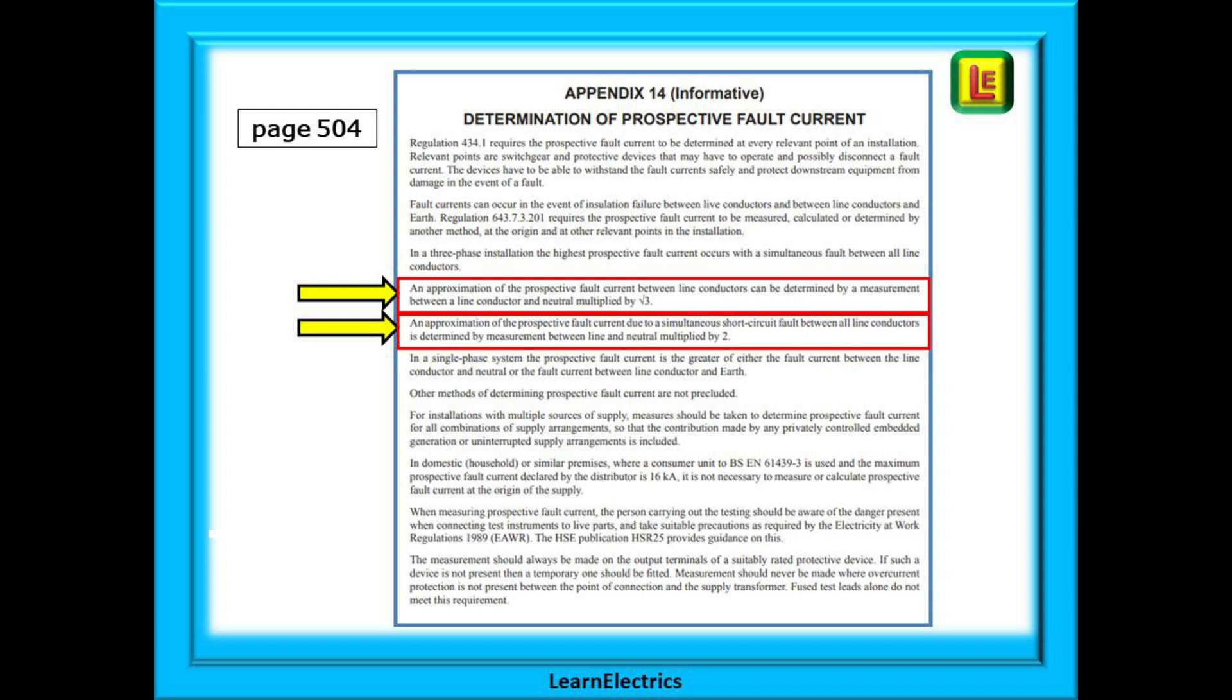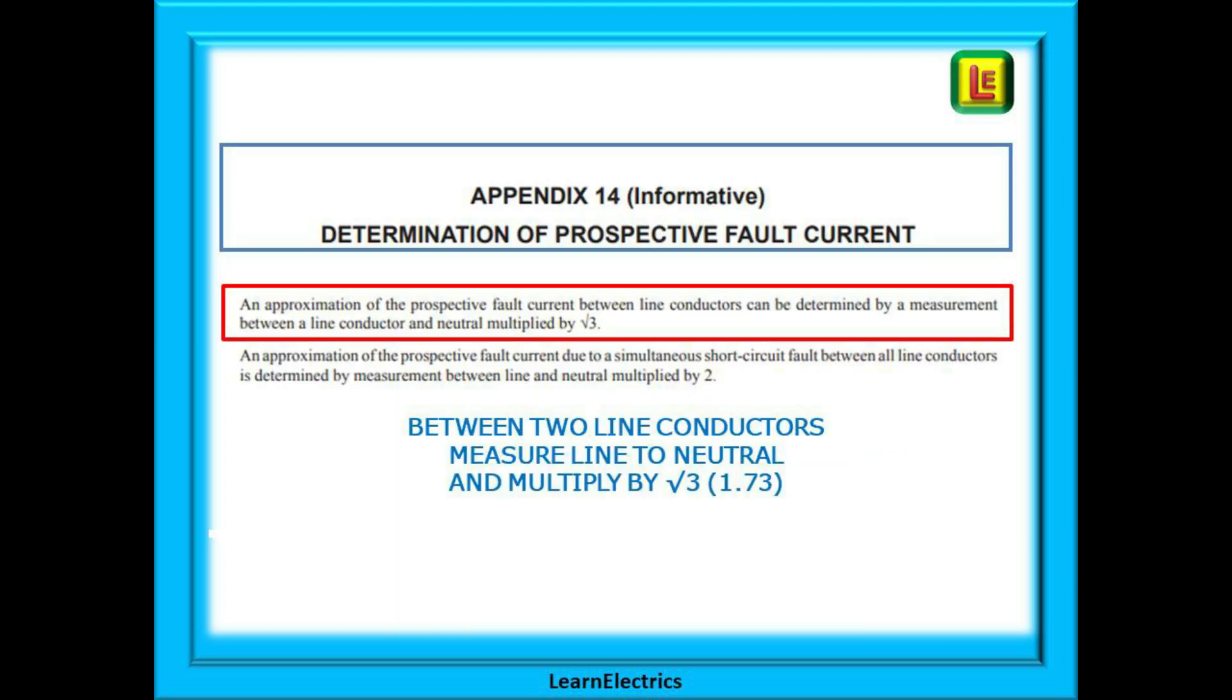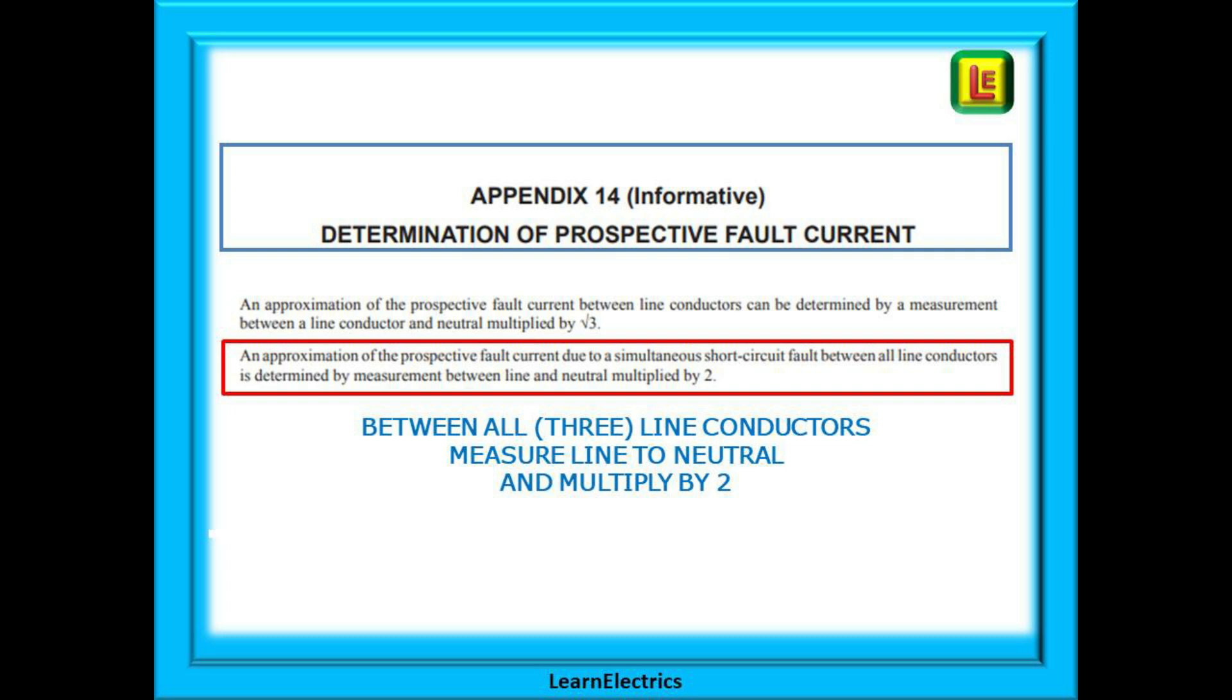We can begin by looking at appendix 14 in the wiring regulations as this is where it all starts. You will find this on page 504 and the two important sentences are highlighted. The first sentence of interest is about a short between two of the line conductors. We can calculate the approximate prospective fault current, the PFC, by first measuring between line and neutral and then multiplying this number by the square root of three, which is 1.73. The second sentence considers a short between all three line conductors at the same time, and it tells us to calculate the fault current by taking the line to neutral value and then multiplying this number by two.